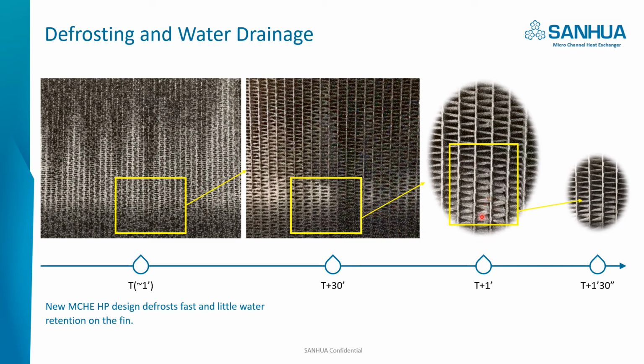And 30 minutes later, we checked the bottom of the coil. We don't see the white frost, and the fin is getting wet. And 30 seconds later, when we check the fin of the bottom coil, we see the fin is clear and dry, so there's little water retention on the fin. And the new microchannel heat pump design defrosts fast.